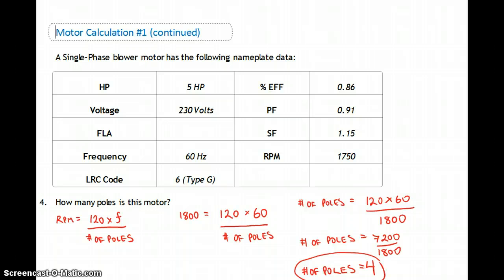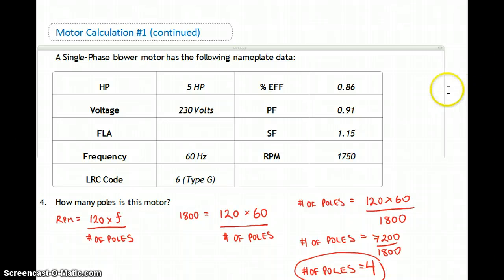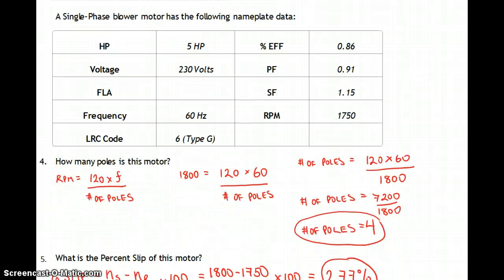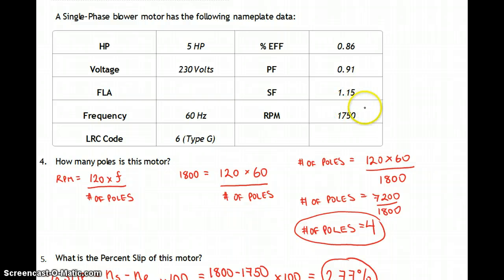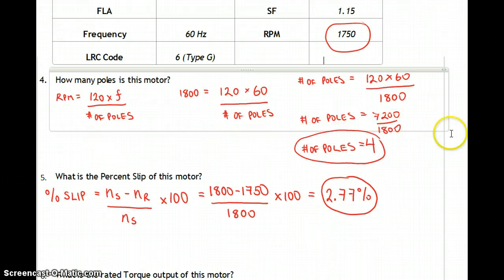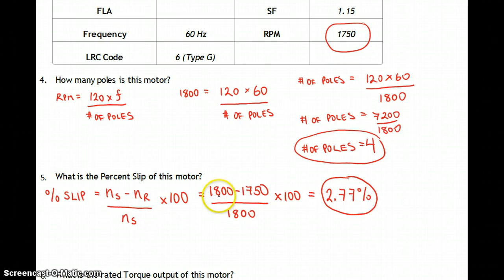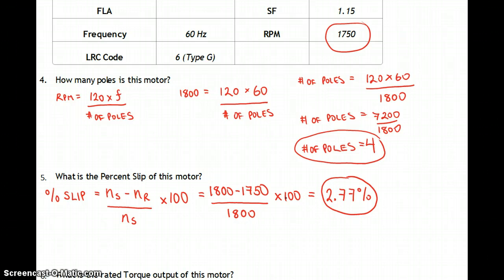Working off the same motor nameplate, how many poles? We established it's a four-pole motor. The calculation is: RPM equals 120 times frequency over number of poles, so 120 times 60 over 4 equals 1,800. Reconfigured: number of poles equals 120 times 60 over 1,800 — four poles. Percent slip: 1,800 minus 1,750 over 1,800 times 100 equals 2.77%.